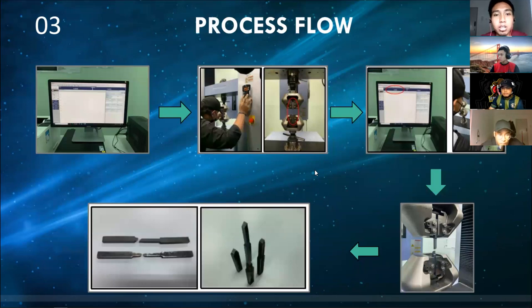So for the process flow, first open the metal file from the Shimadzu software and click tensile test. After that, second, put the specimen in the top grip and tighten it in place, being careful not to bend the specimen while tightening. Third, set the position and force to zero in the system. Fourth, start the test by pressing the start button and wait until the specimen breaks, then save the data result in a PDF file.